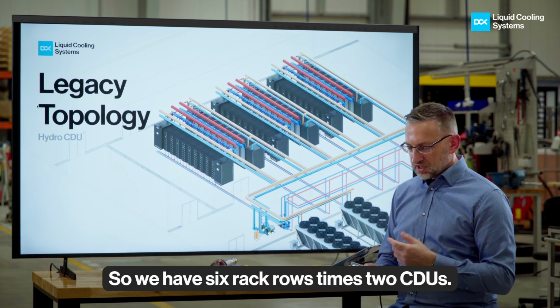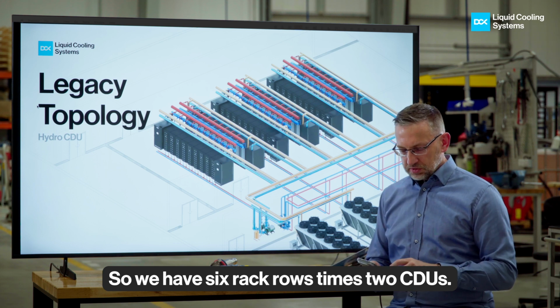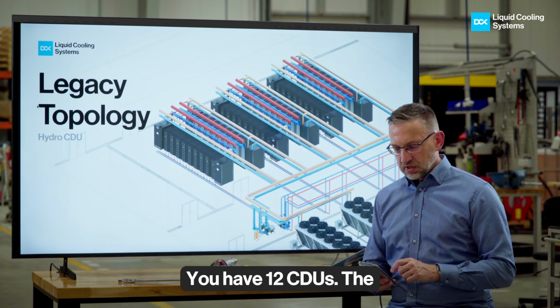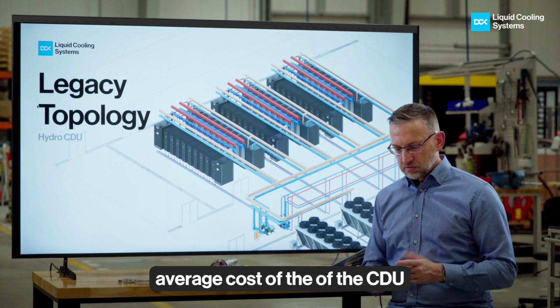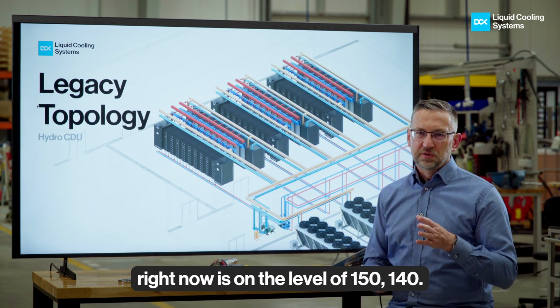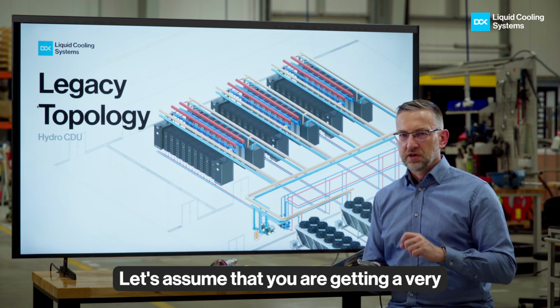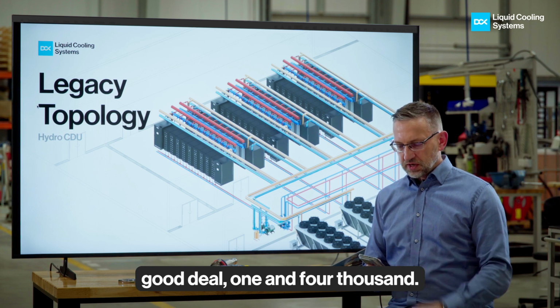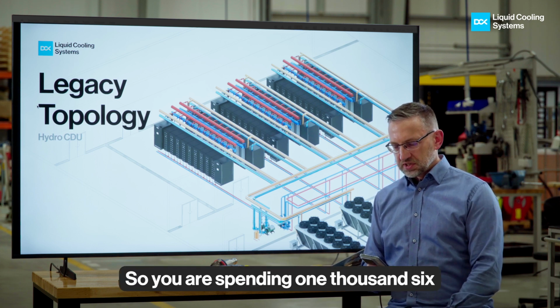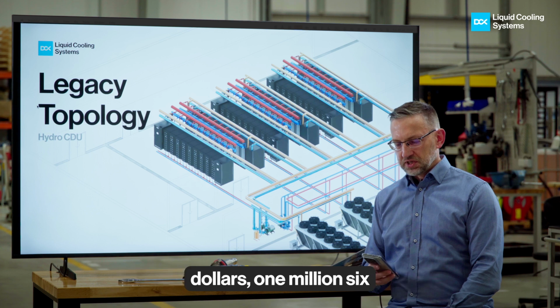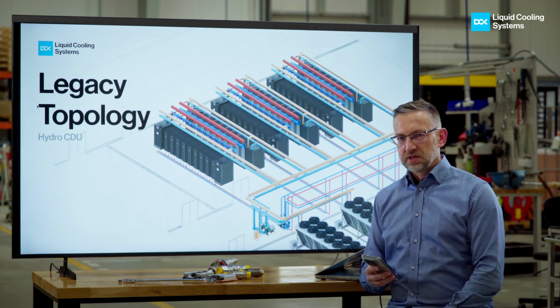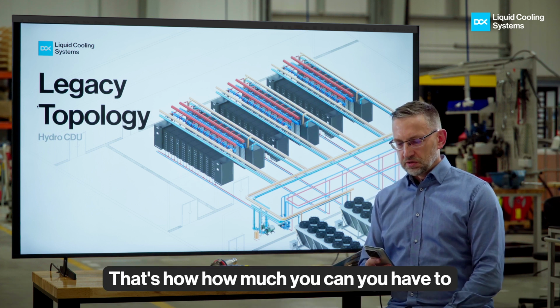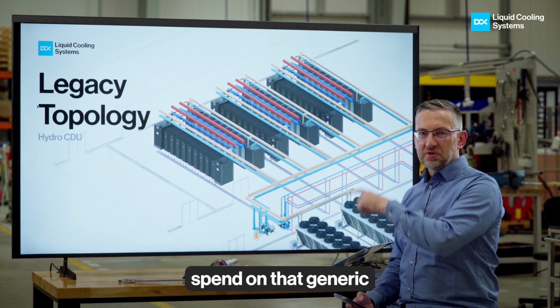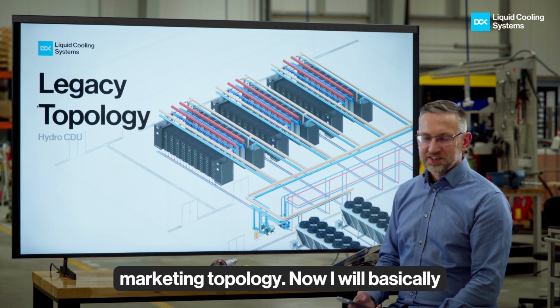So we have 6 rack rows times 2 CDUs. You have 12 CDUs. The average cost of the CDU right now is on the level of 150, 140. Let's assume you are getting a very good deal, 140,000. So you're spending $1,680,000. That's how much you have to spend on that generic marketing topology.